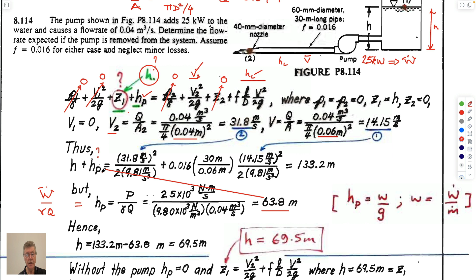HP, power, is equal to 25 times 10 to the 3 Newton meters per second, watts, divided by 9.8 times 10 to the 3 newtons per meter cubed, 9.8 kilonewtons per meter cubed, and the volumetric flow rate is 63.8. If we put 63.8 meters in here, we're left with only one term, the value of H, which turns out to be 69.5 meters.